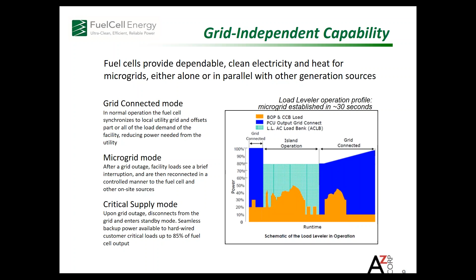And then finally, we have our critical supply mode. The critical supply mode takes power hardwired from what we call our customer critical bus, and it hardwires that power into critical loads on the customer side. In that sense, the breaker that connects the customer critical bus over to the customer critical load is not subject to interruption or opening in the case of a grid outage. So we can continue to flow power from our customer critical bus when the grid goes away, whereas in microgrid mode, we're connecting through our tiebreaker that does need to open, so you see a temporary interruption of power in that mode. So to summarize then, the microgrid mode, we refer to it as a drop and pickup scheme. You see about a 1-minute interruption in power flowing from the fuel cell to the facility. In the critical supply mode, there is no interruption, and it is a seamless provision of power to the customer's load.